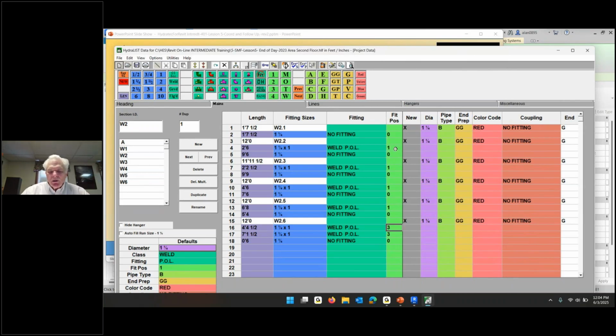So I think these are up, over, and down, and this one is down, over, and down, and they're all 1 inch because of the arm overs being 1 inch. Okay, so I've got a sense of where that is. It's one of those long branch lines that goes across the whole second floor from left to right. W2 has got a 12, an almost 12, 12, 12, 12. So mostly the same thing.